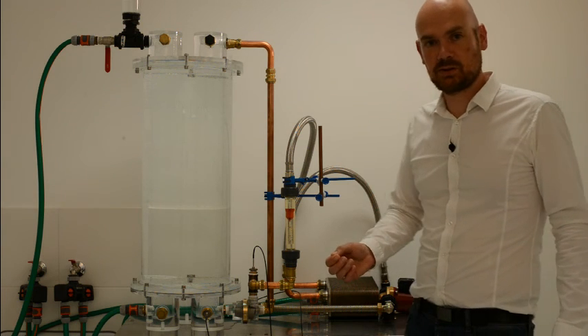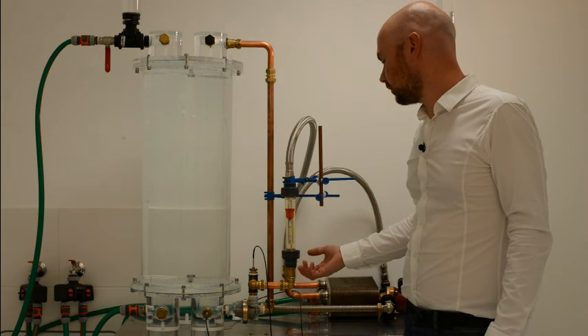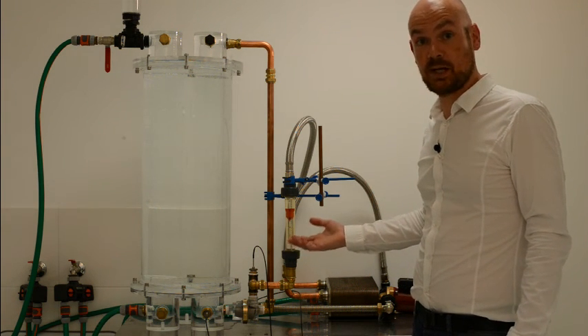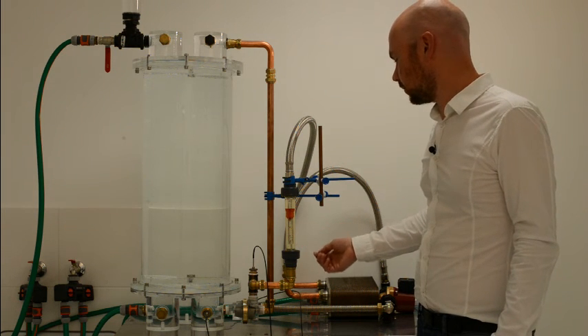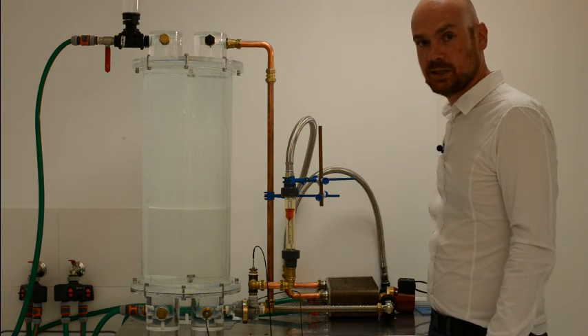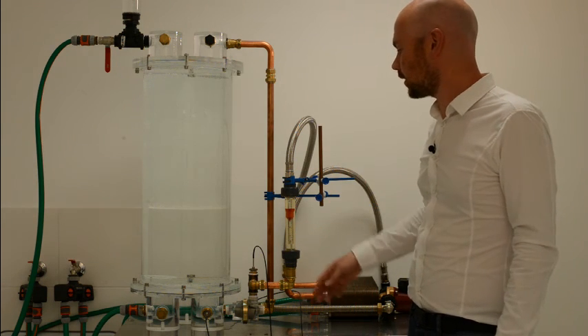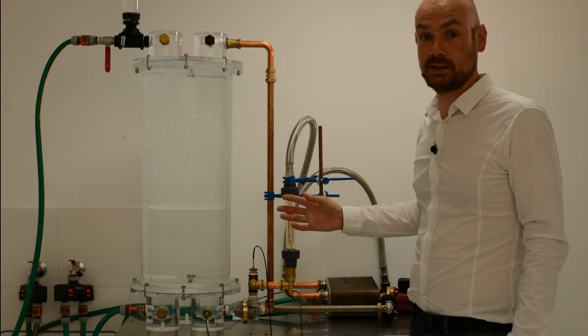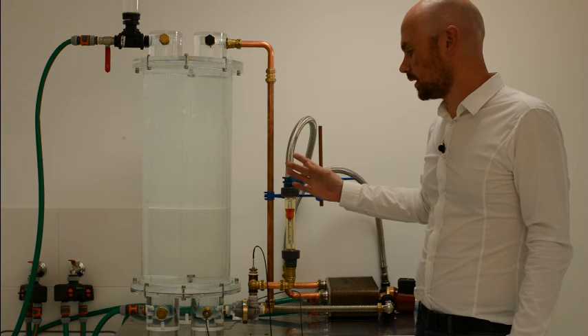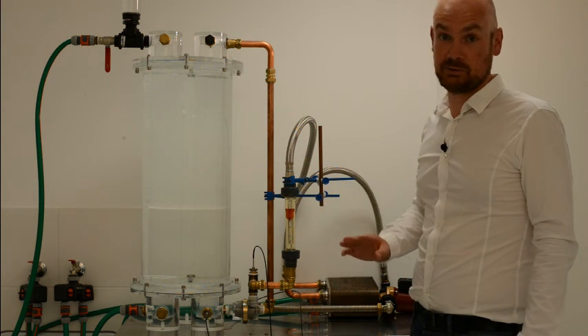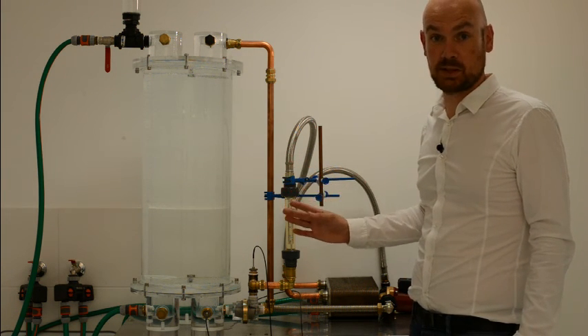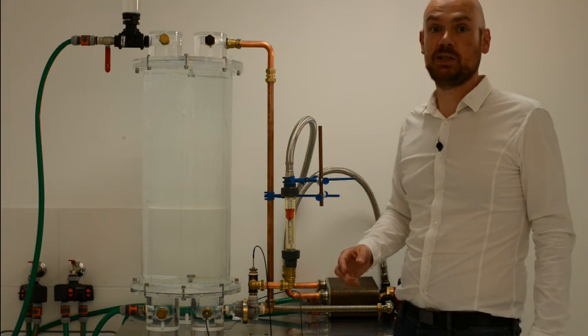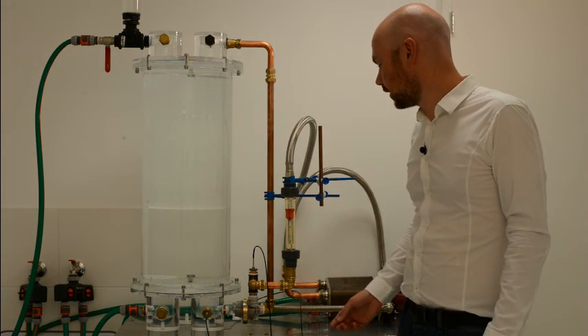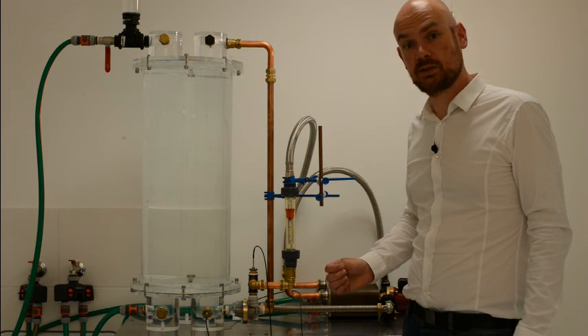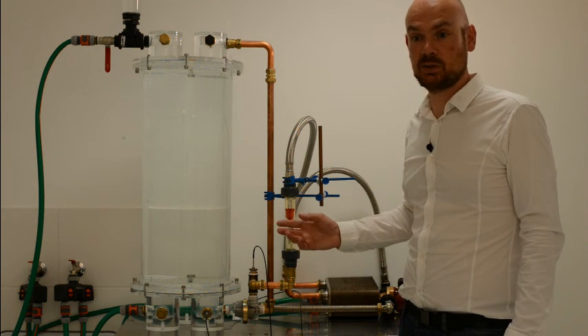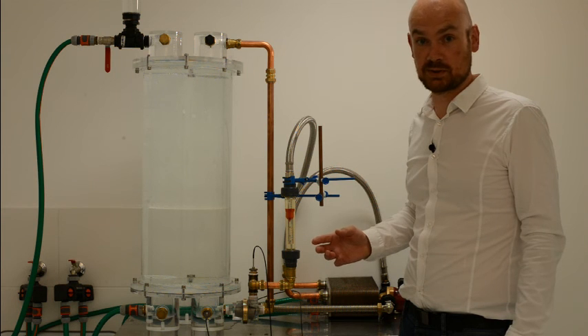And so the valve will then take care of the differential control element of the system, because it will make sure that the circulation through the solar panel will only pass through your solar tank when it can actually deliver heat. But at times when there is very low irradiation and your tank might be very hot, your solar panel will not be able to deliver heat, and in that case the valve will bypass your solar storage tank to make sure that no heat is withdrawn from the system.